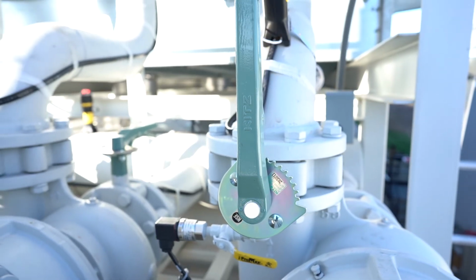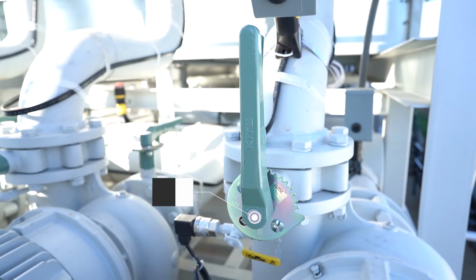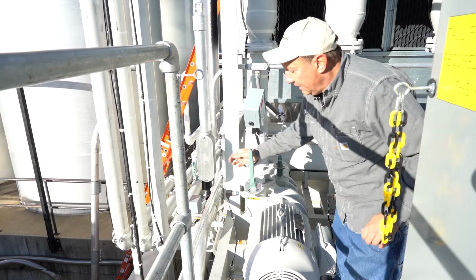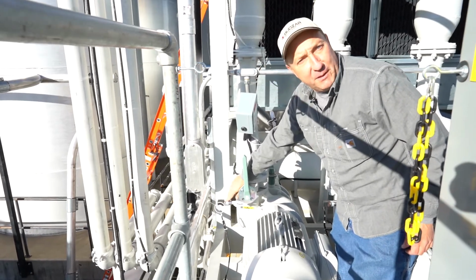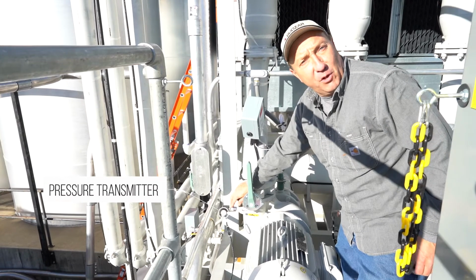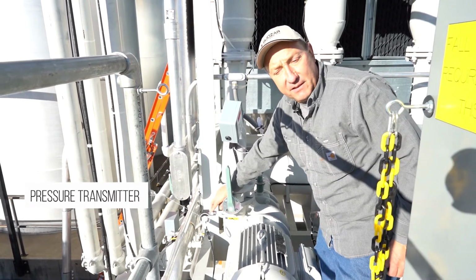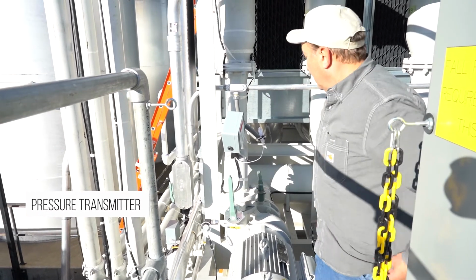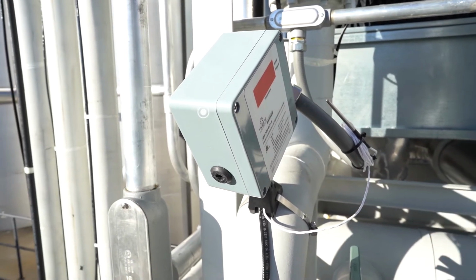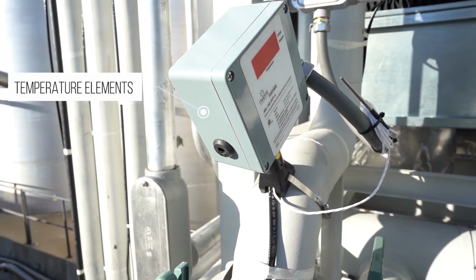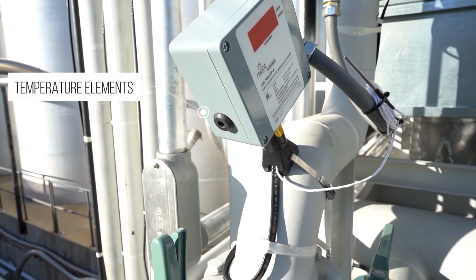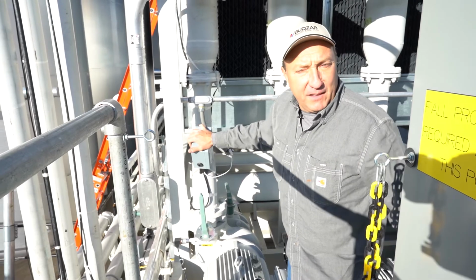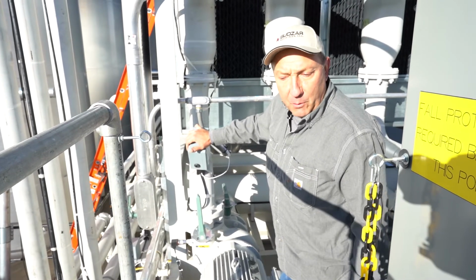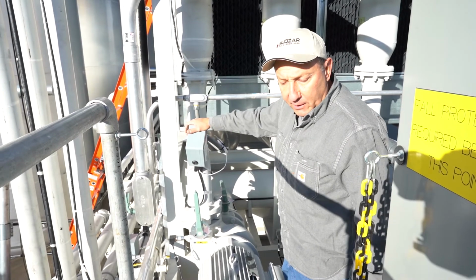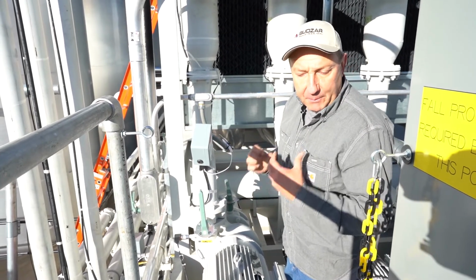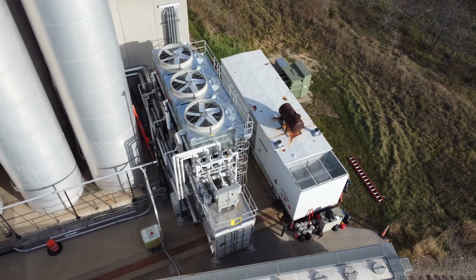Okay, each individual pump, as I stated, can be isolated with the butterfly valves. Each one has a pressure transmitter, so we can see the pressure and flow rate displayed on the HMI down inside the container, the control panel. We have temperature elements that control the heat trace. You don't need the heat trace in the warmer temperature. I believe we're going to have this set to turn on around 40 degrees Fahrenheit, and the heat trace will be underneath the insulation to keep the pipes from freezing in the inclement cold weather.